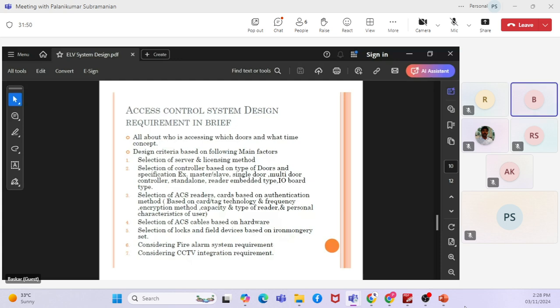And the fourth one is the ACS cables. Access control cables are not common. It varies depending on the type of field devices we are connecting. Let's say a push button for exiting the door will have a 2-wire system, and for the reader you will have 6-wire or 8-wire. So depending on the manufacturer requirement, the cable has to be chosen. Apart from that, there is a standard criteria also. If you go with a push button on a 2-wire system and a lock on a 2-wire with a thick cable, the gauge of the cable will be more, and for the reader it's more multi-strand cables with 4-wire, 6-wire or 8-wire, based on the connectivity and the technology, as I said, Wiegand or OSDP. And selection of locks and field devices is based on the ironmongery set as well.